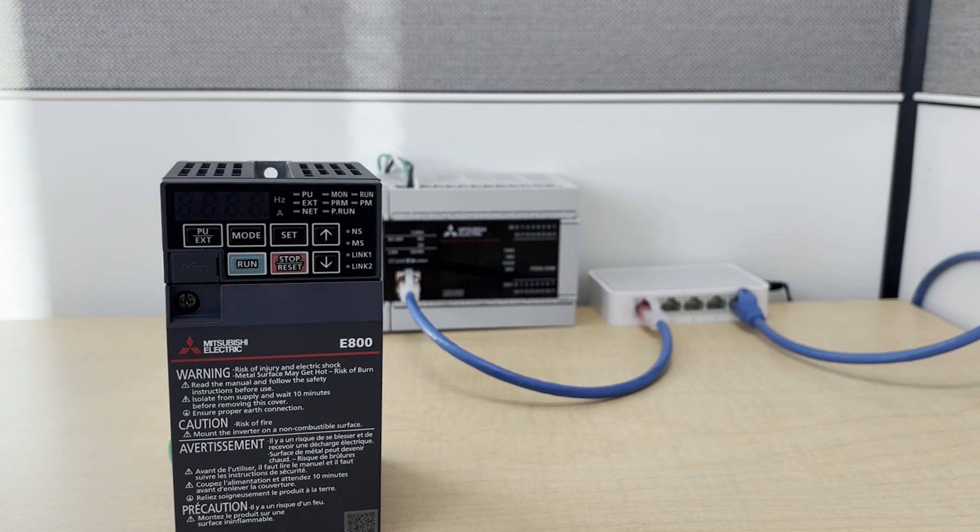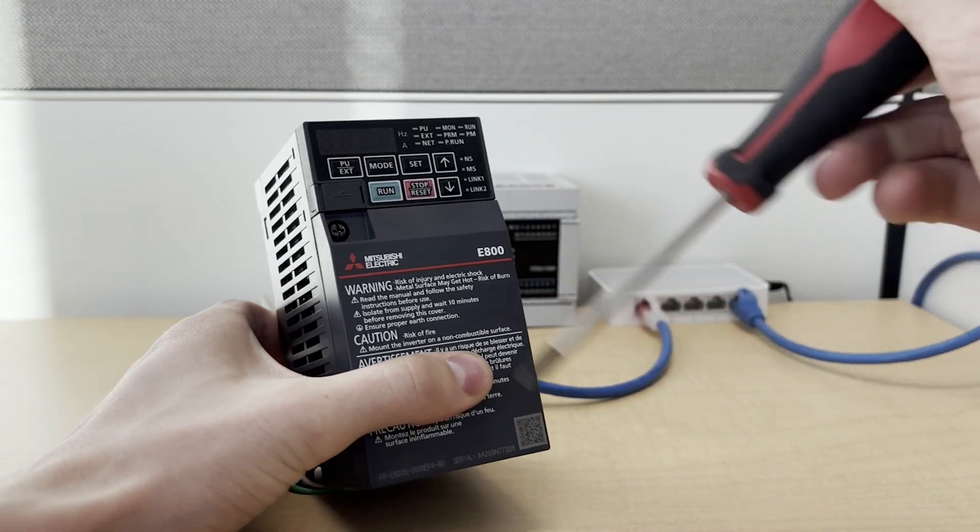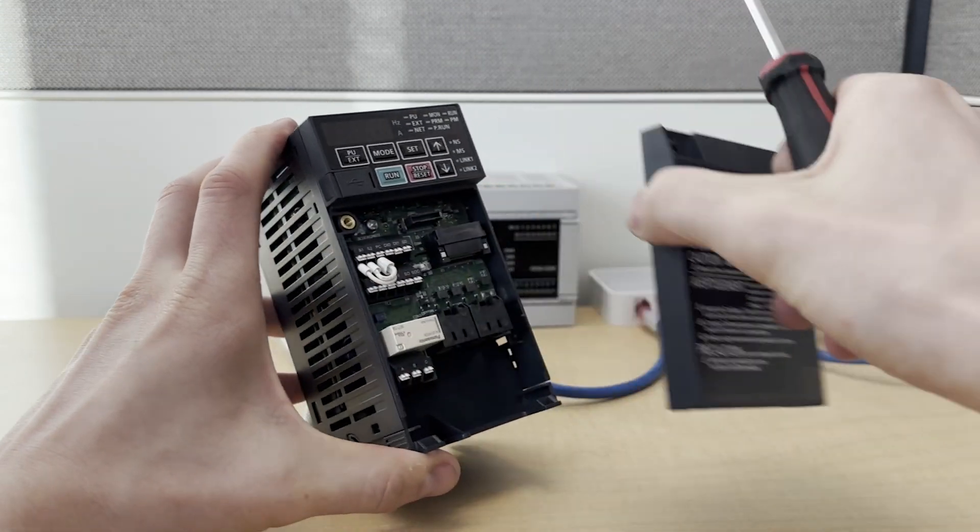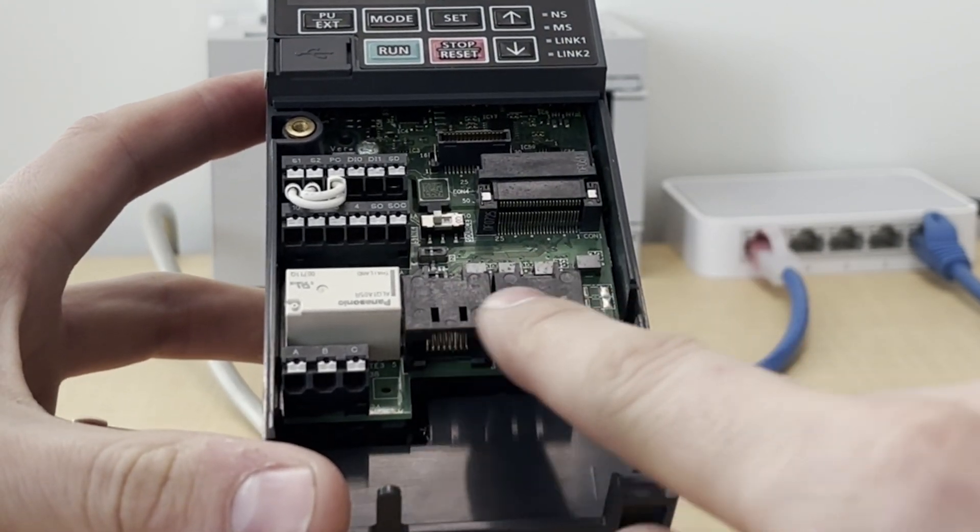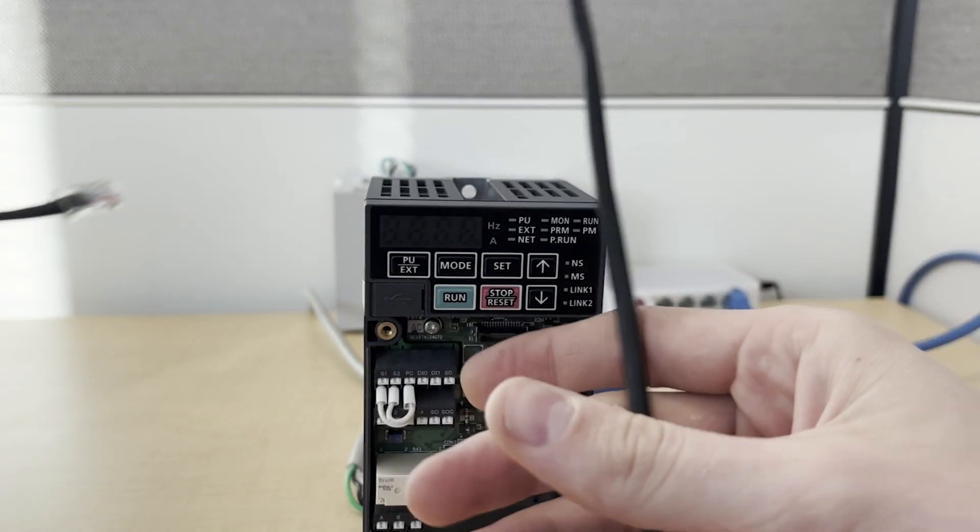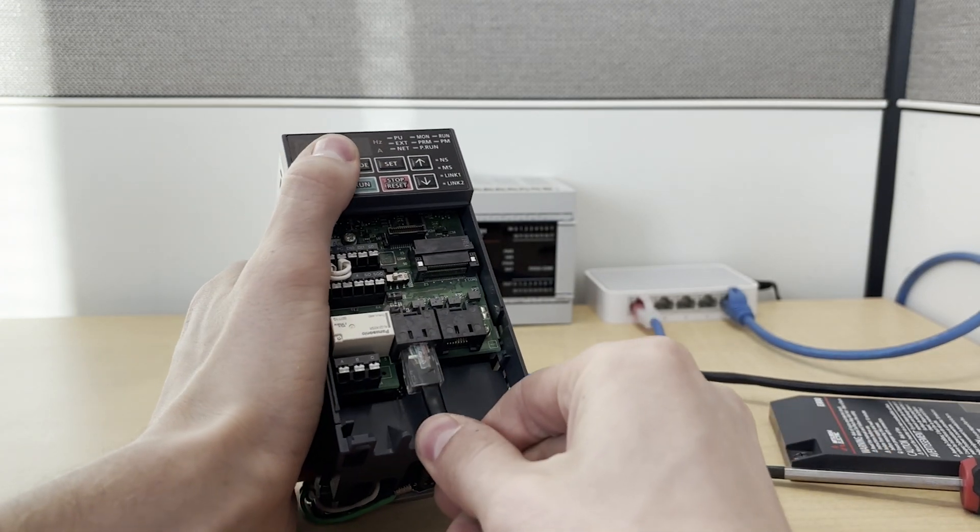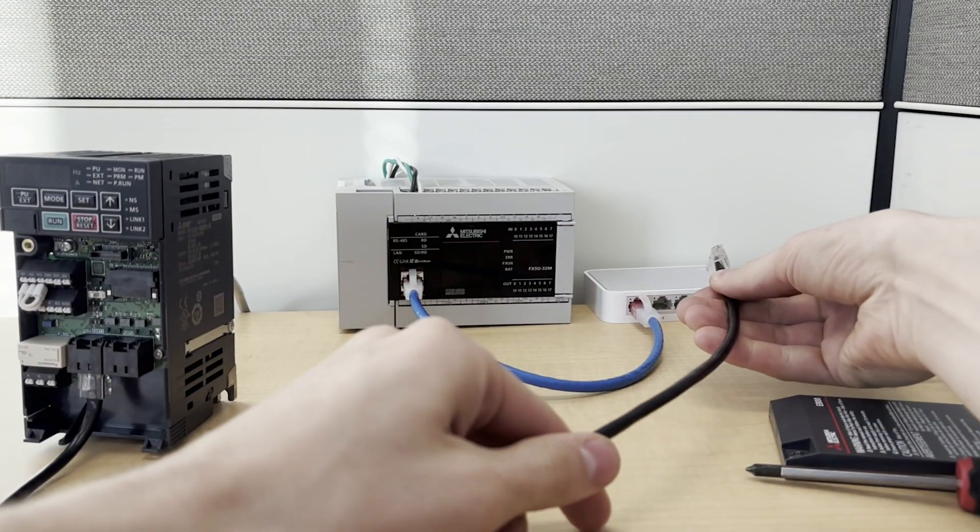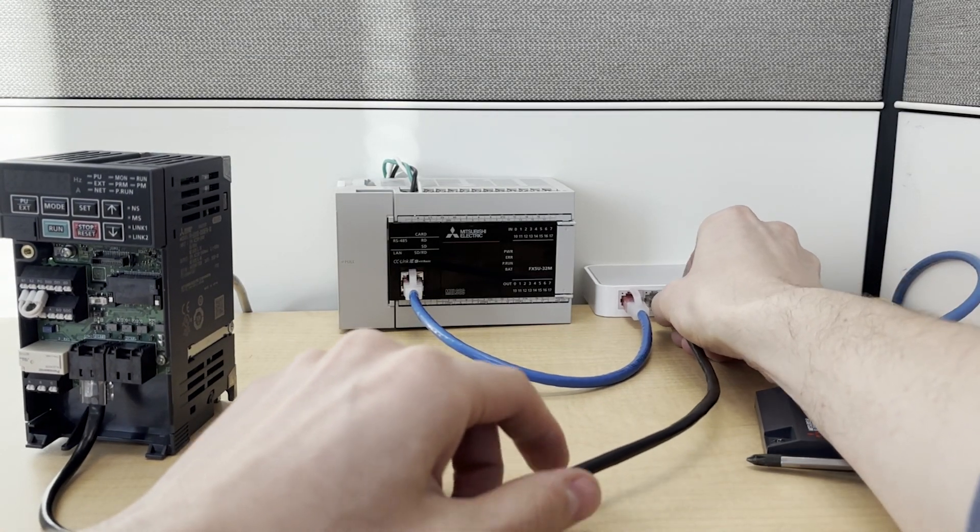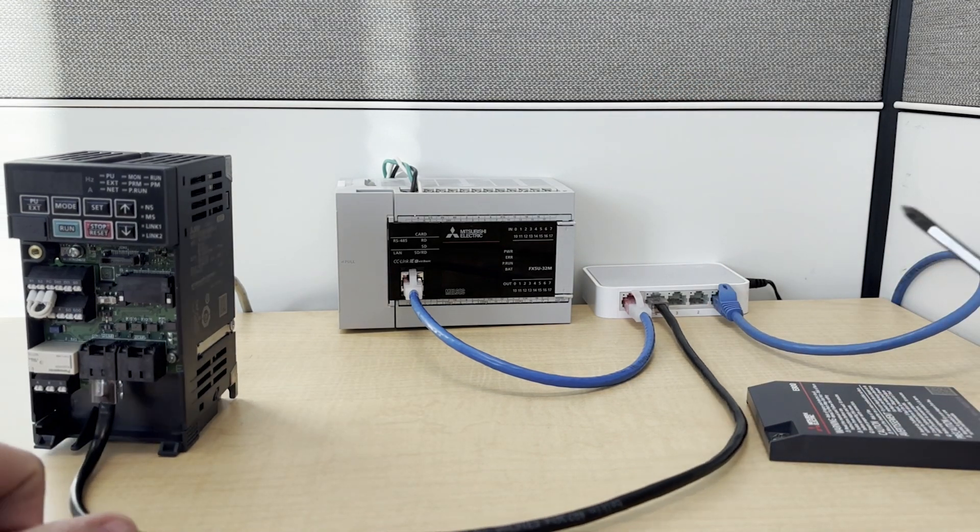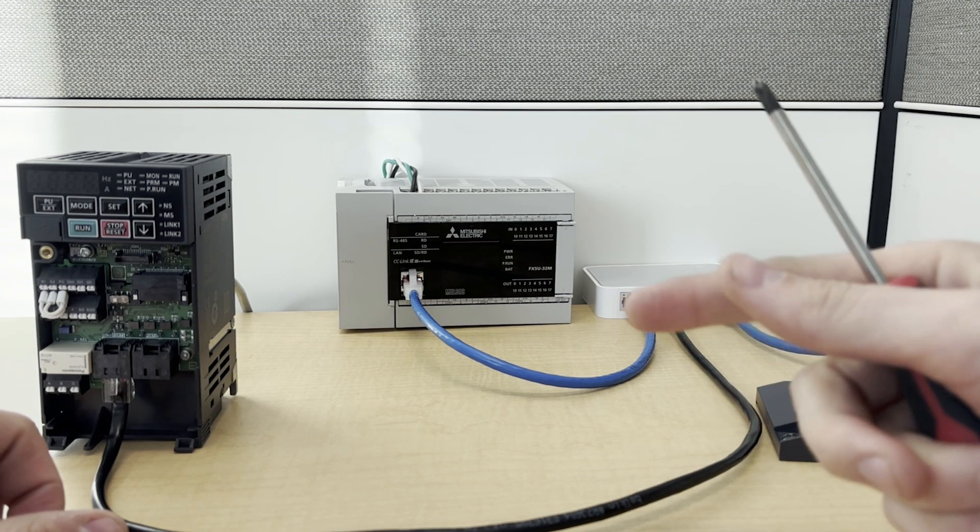While the power is off, this is a convenient time to remove the front cover and connect the Ethernet cable. The screw here will allow you to remove the front cover. On the front here, we can see two Ethernet ports for an RJ45 connector. Grab my Ethernet cord, connect it to either of the ports. And then we'll connect the other side to our switch. You may connect it directly to your FX5U CPU or an Ethernet module. We're going to be running through a switch today so that I can program and monitor it from my PC without having to disconnect anything.